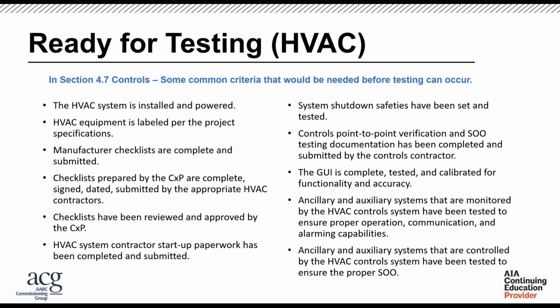So you want to make sure that when we're testing, we're testing in the final condition that the room will be in. And the same thing applies when you're looking at terminal units. You want to make sure that everything is in there, all your ceiling tiles are in. If you're doing ceiling tiles, your VRFs, you also have the manufacturer come in and do their startup and programming. Sometimes you have two separate controls. You might have individual equipment controls tied with system controls. So you want to make sure that coordination is done.